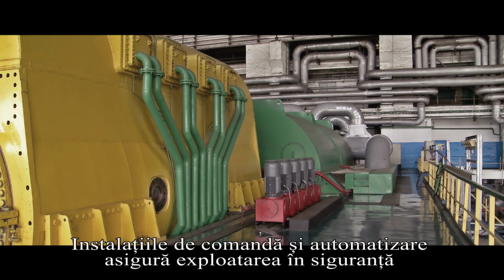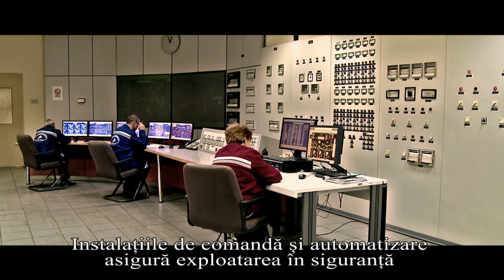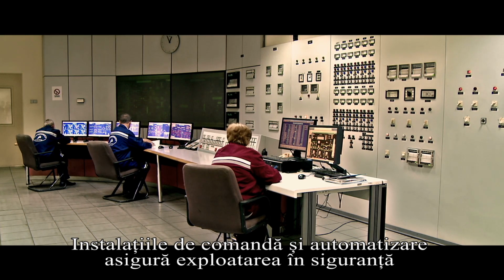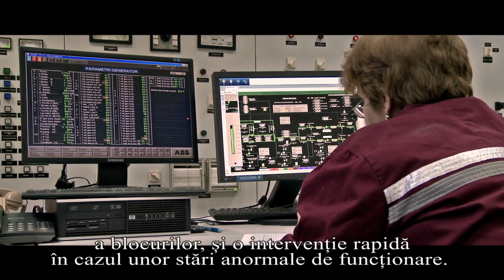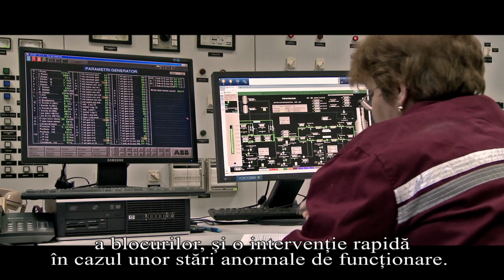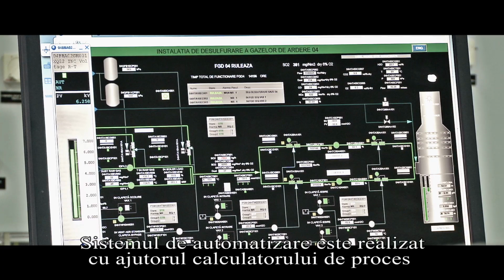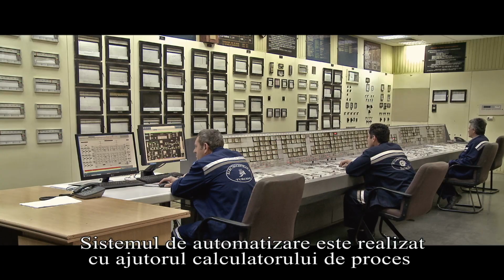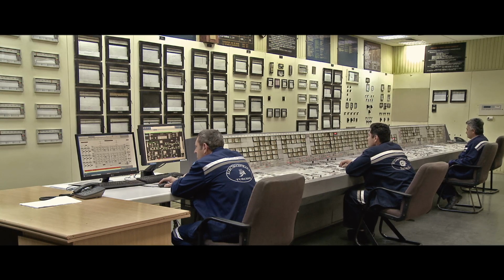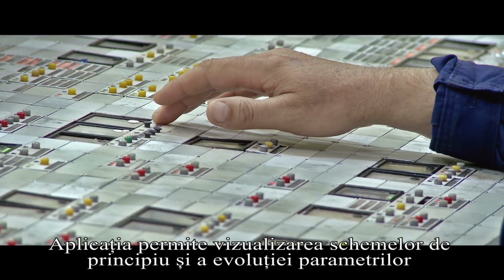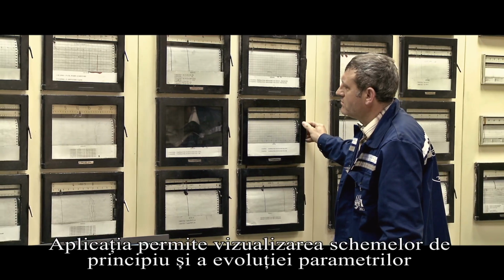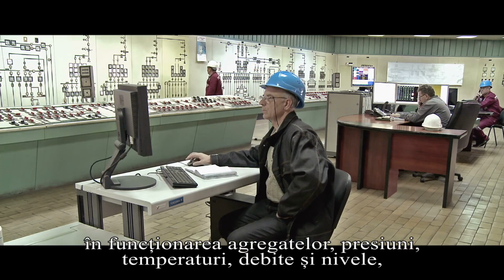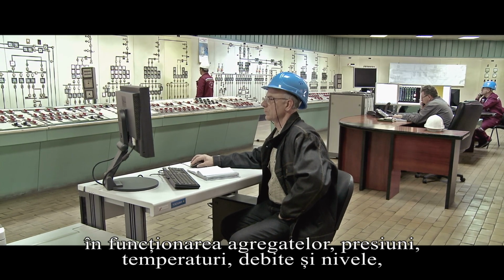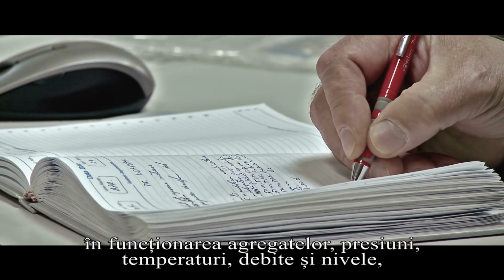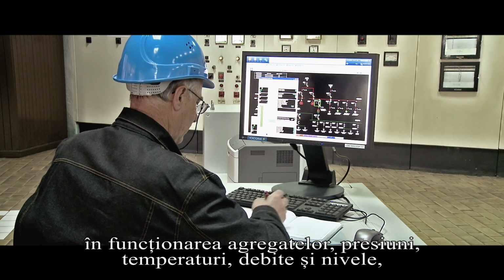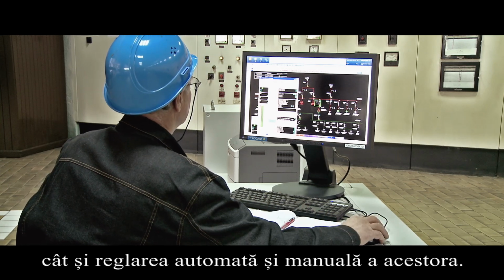The two power plants are similar inside the machinery hall, as they have been modernized since 1990. The command and automation equipment ensures safe operation of the units and fast intervention in case of abnormal operation. The automation system uses a process computer and control loops. The application allows viewing the principal schemes and parameter evolution in the functioning of the machines - pressure, temperature, flow and level - and also their automatic or manual adjustment.